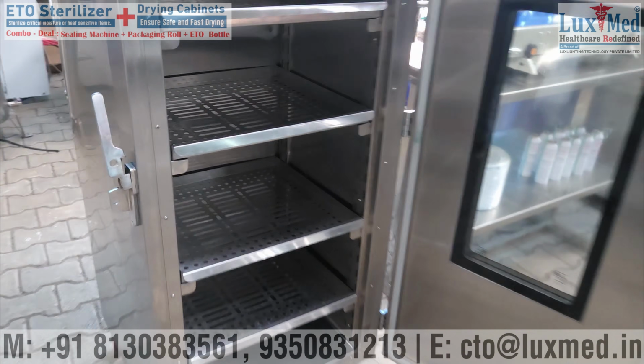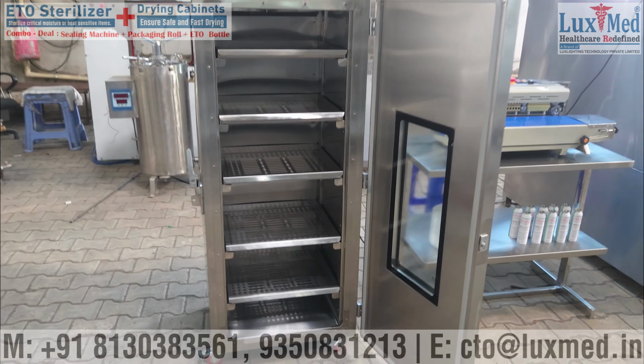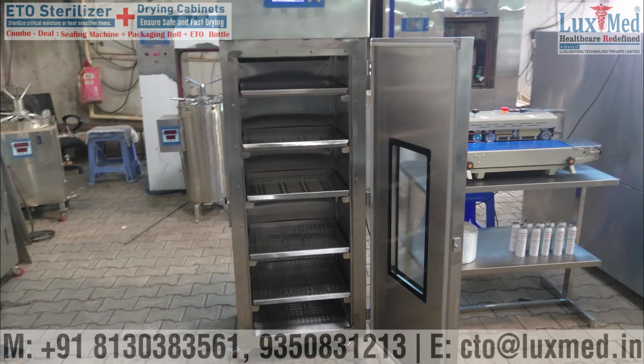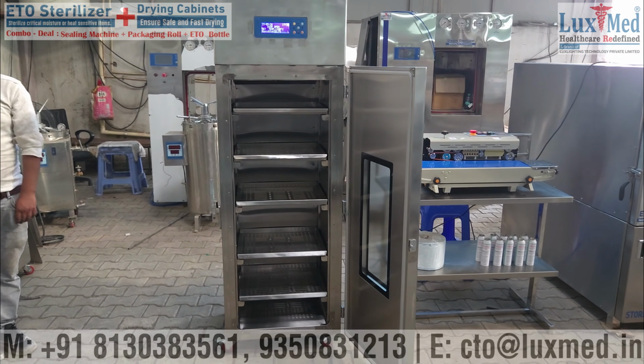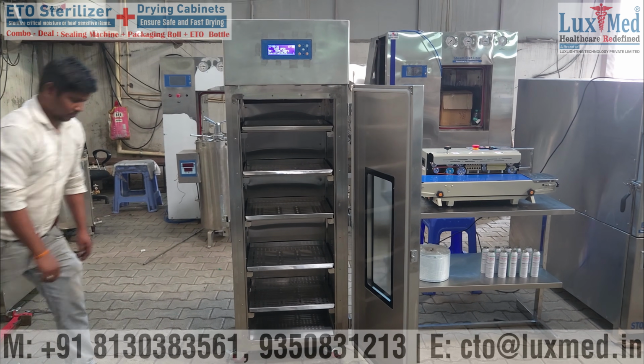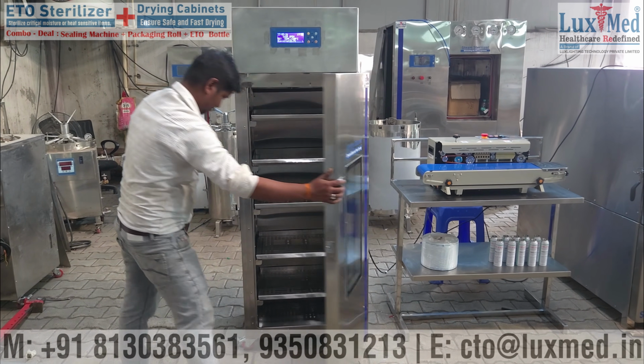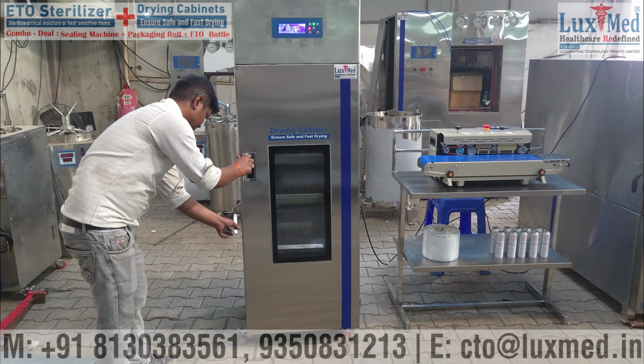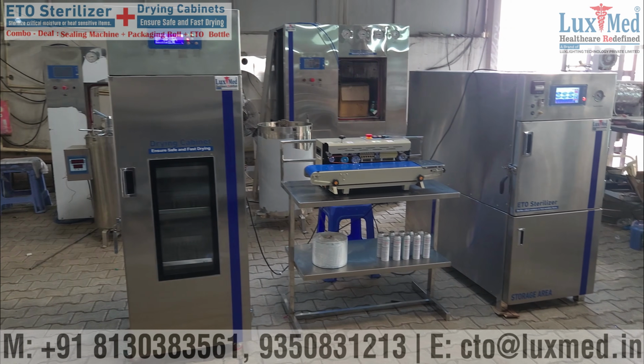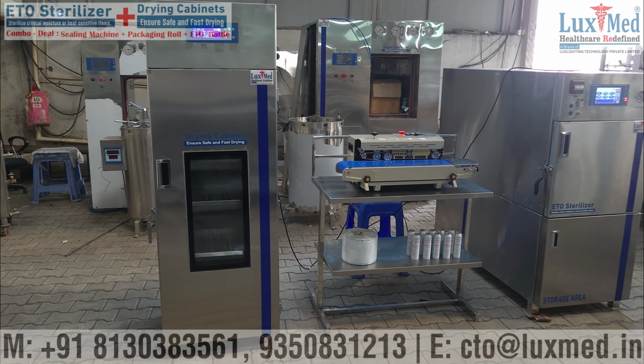The process. The cycle requires 4 critical parameters to function: ETO gas concentration, temperature, relative humidity, and exposure time. It typically requires 1 to 6 hours of exposure, followed by an aeration phase to remove any residual toxic gas before the equipment is safe to handle.